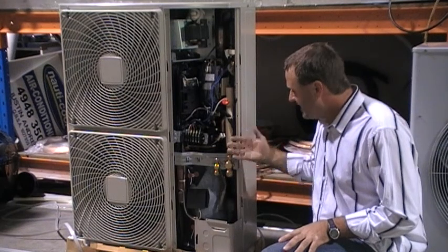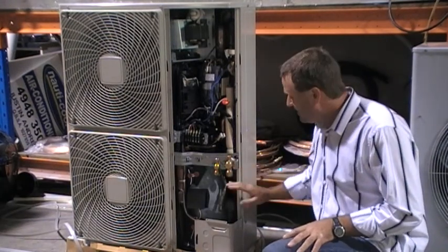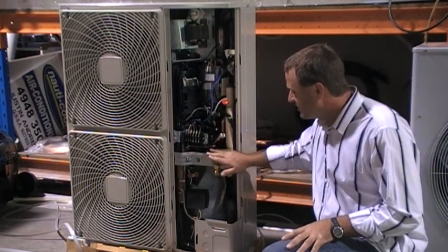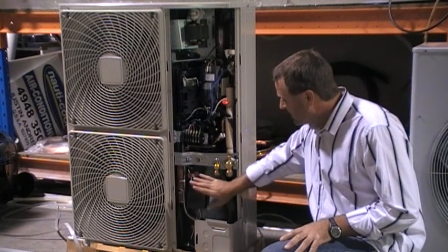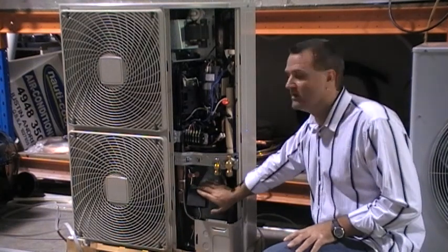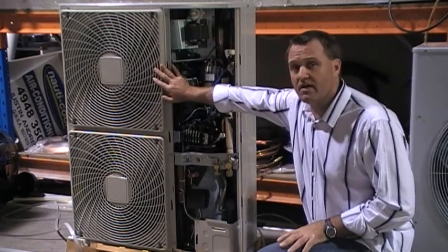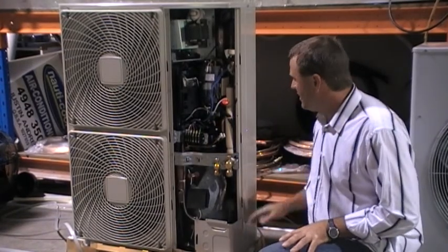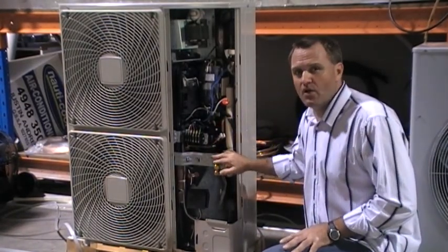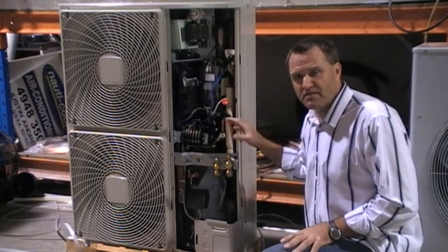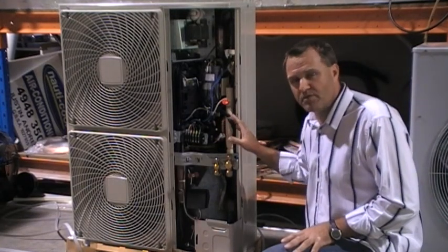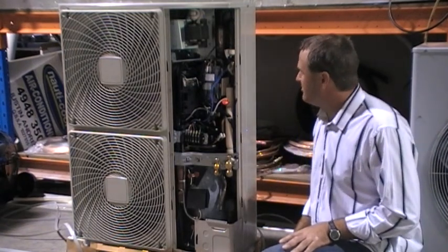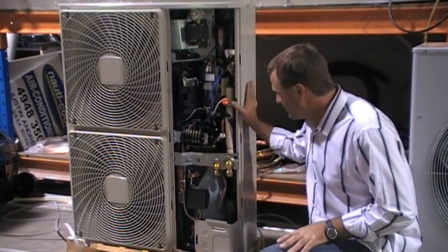The advantages with the inverter system are power savings, because you're getting a unit that will actually ramp down. You're getting a compressor that will start softly. You're getting condenser fans that also have inverter drives in them that start softly and gradually ramp their way up. Inverter units won't dim your lights and that sort of thing if you have power problems like the old standard cycling units used to. They would be the main advantage with an inverter.